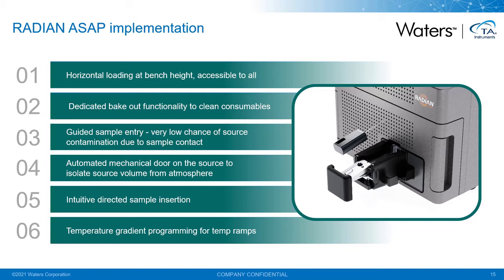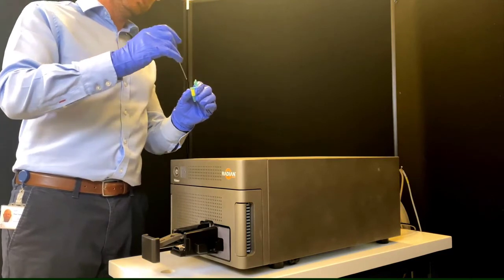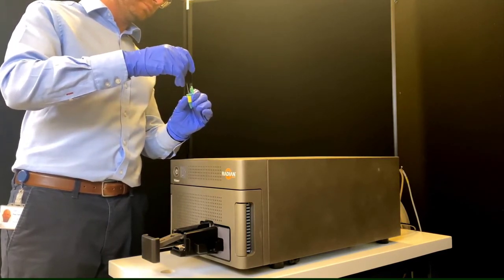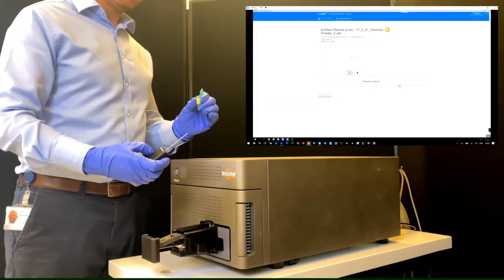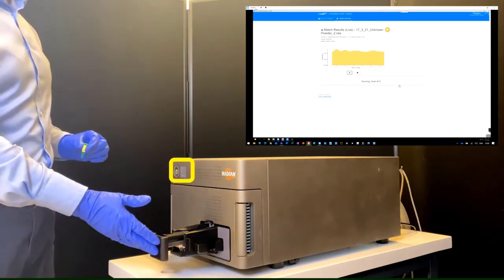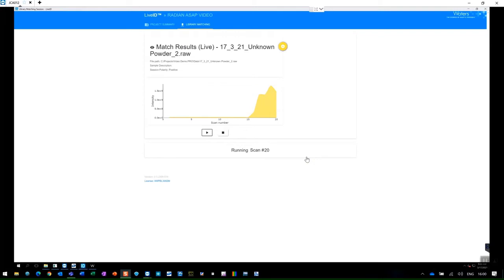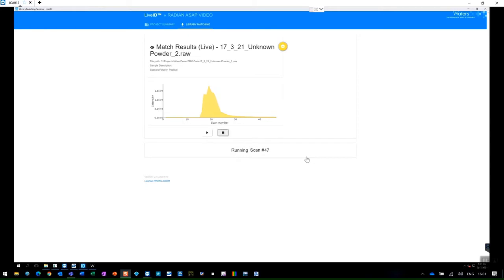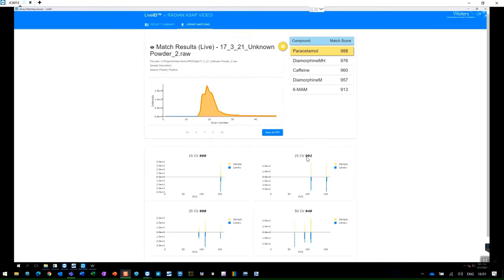I'm going to show you a few examples of different applications investigated with Radian ASAP, starting with a short video clip of one of our application scientists performing a real-time library matching experiment with LiveID on a sample of seized drugs. After cleaning the capillary, one method of sampling is to dip the glass capillary into a solution of the seized sample and swirl it for a few seconds. The glass capillary is then placed into the sample loader, which automatically triggers the instrument to start acquiring background data and the method LED on the front of the instrument starts flashing. When it stops flashing, you push the sample into the instrument and start collecting data from your sample. LiveID then detects the peak automatically and matches the acquired data with the library to determine which compounds are present.